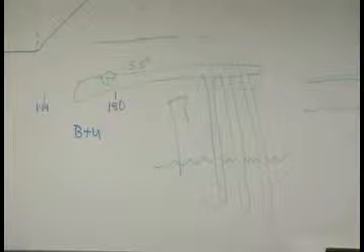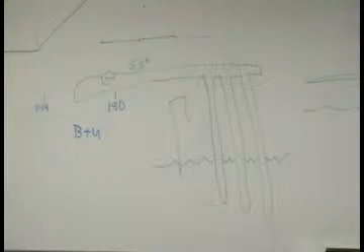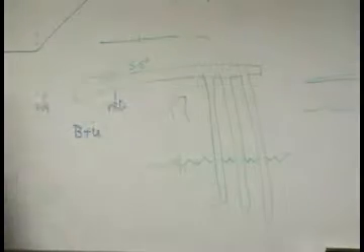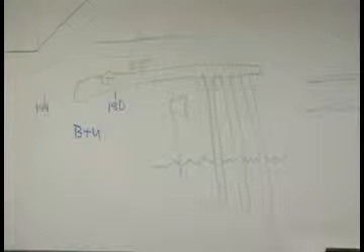It really is. They built 2 identical schools in Lincoln, high schools. They are absolutely identical. The well fields are identical in number. One of them, in the summer, our loop temp warms up to 80 degrees. It gets hot. Southwest gets hot. North Star, on a 100-degree day, is running at 58, 59 degrees. There must be a big difference in the soil. Something down there, the water table, the soil, for some reason one of them cannot get rid of that heat. It doesn't seem to be a problem in the winter.